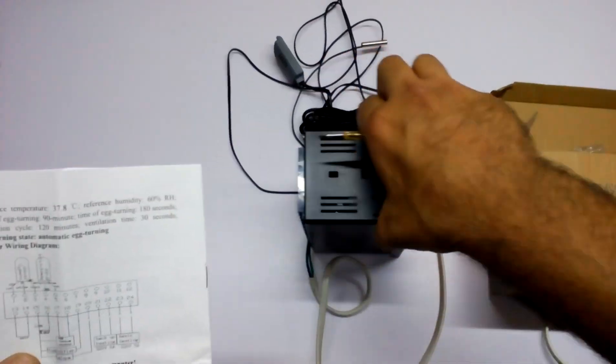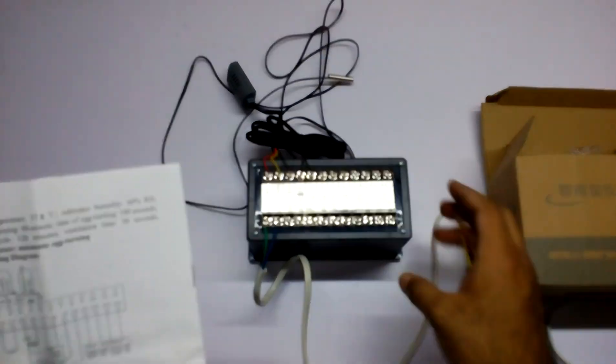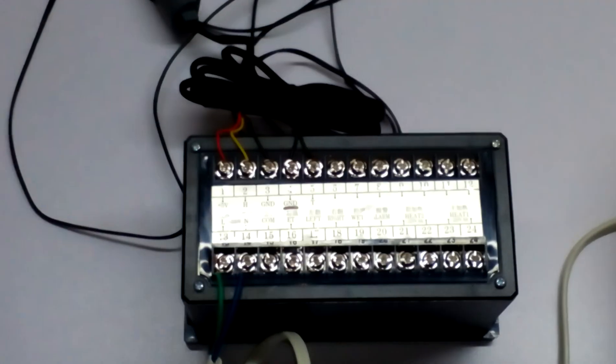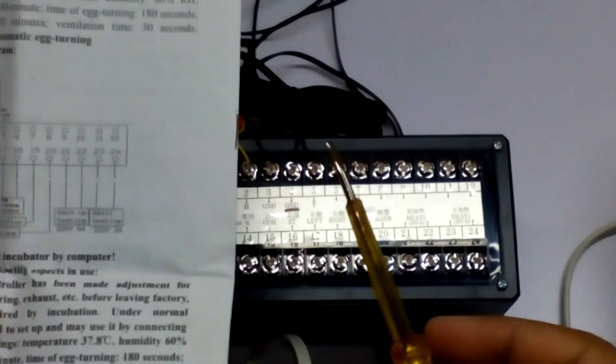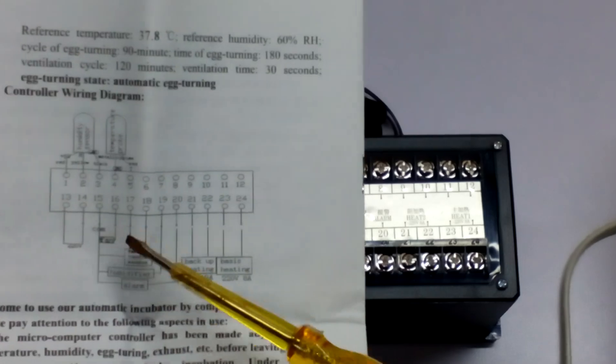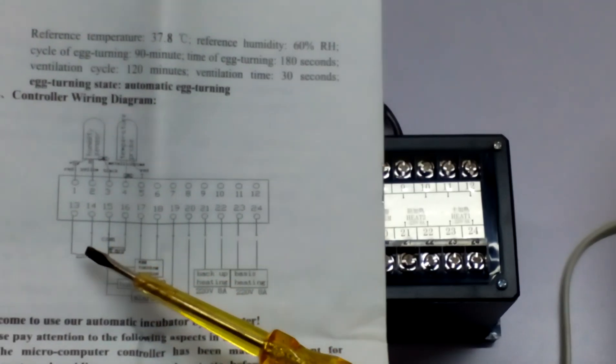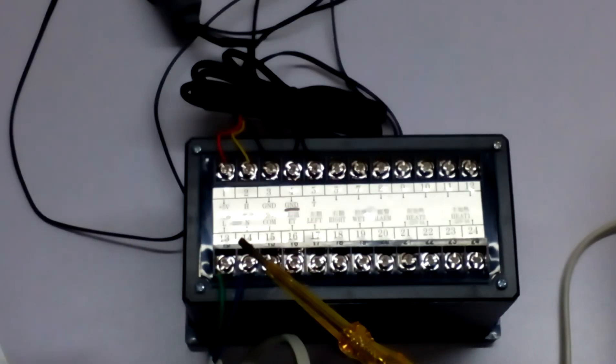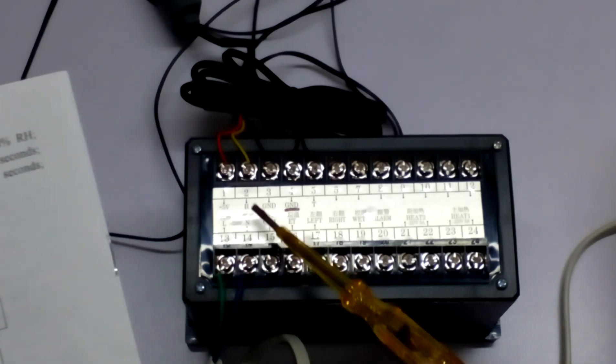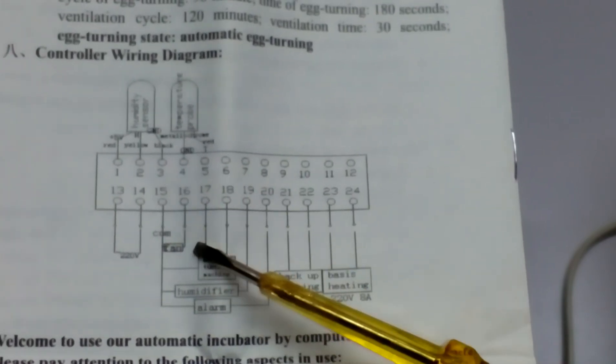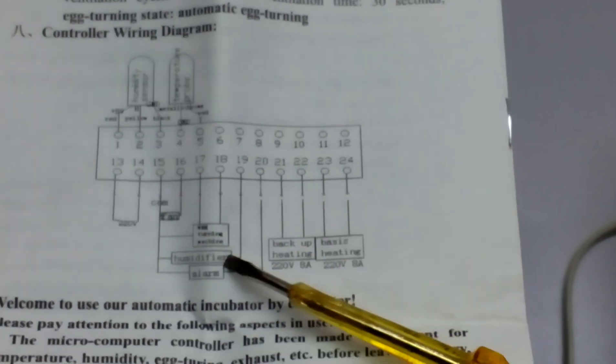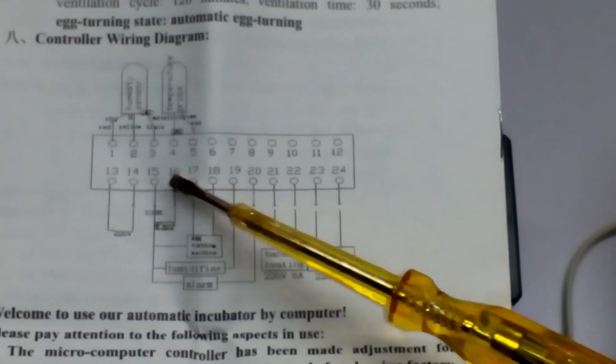If we look at the back side, these are the things to note. It is powered by 220 voltage which will connect to pins 13 and 14, neutral and load. After that we have the fan, humidifier, and alarm connections.